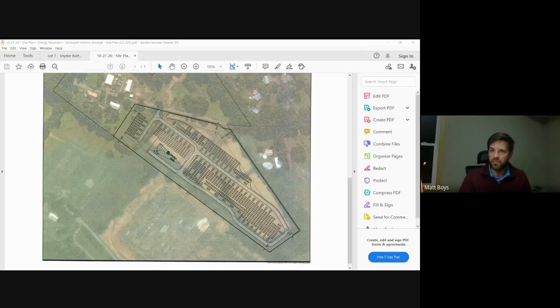Those specialized battery storage containers will sit on cement pads. In between all the cement pads, we typically just have gravel, some type of stone or rock. About 2 to 4 of the battery storage containers will connect underground with cabling into inverters, and those inverters connect with underground cabling to our project substation, which hits the transformer. That transformer moves the electricity up to a transmission level, and then there'll be a couple poles that connect to the existing substation adjacent to the site.